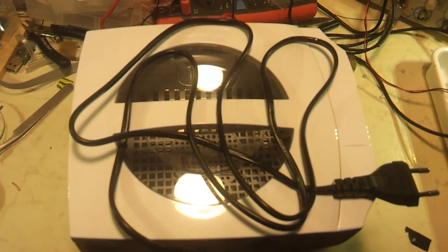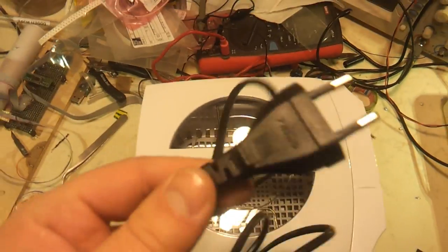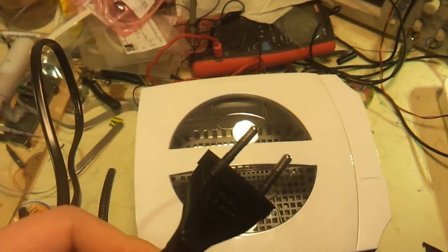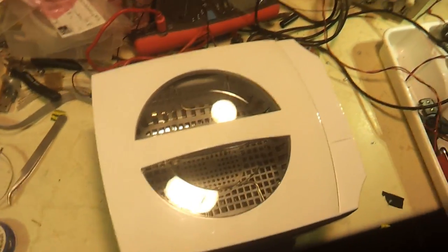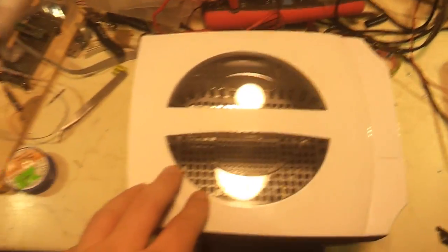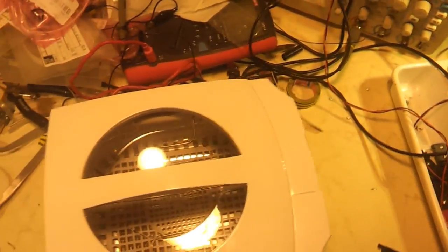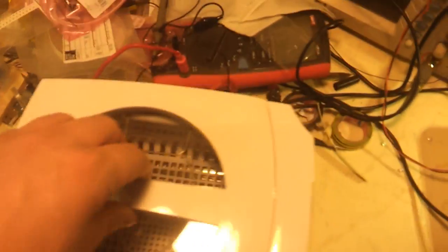Okay, so here's the device itself. It has only a normal cable, no earth grounding. But in general, no wonder. This is a type of device which is meant to be shielded, to be isolated everywhere. I mean, there is no exposed metal that would be mains connected, other than obviously the steel tank inside.